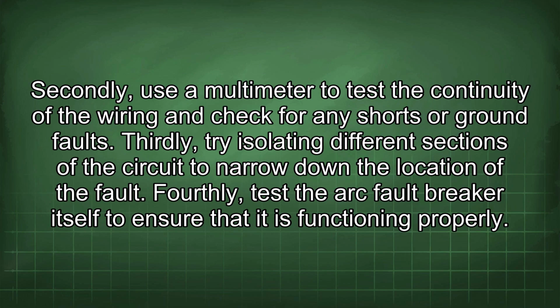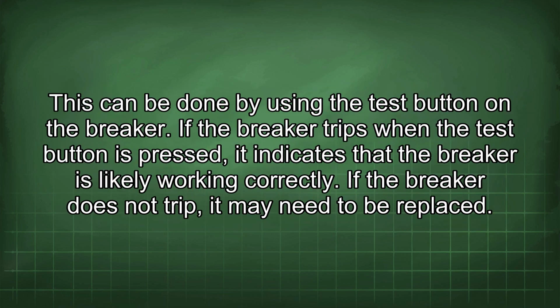installation. Secondly, use a multimeter to test the continuity of the wiring and check for any shorts or ground faults. Thirdly, try isolating different sections of the circuit to narrow down the location of the fault. Fourthly, test the arc fault breaker itself to ensure that it is functioning properly. This can be done by using the test button on the breaker. If the breaker trips when the test button is pressed, it indicates that the breaker is likely working correctly. If the breaker does not trip, it may need to be replaced.